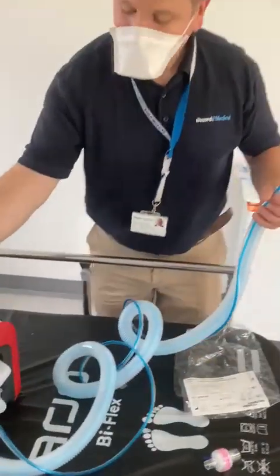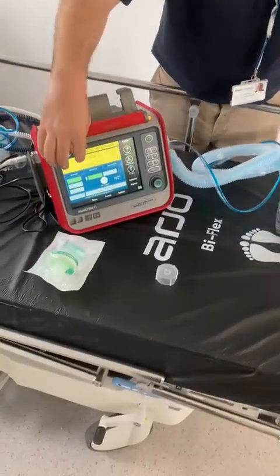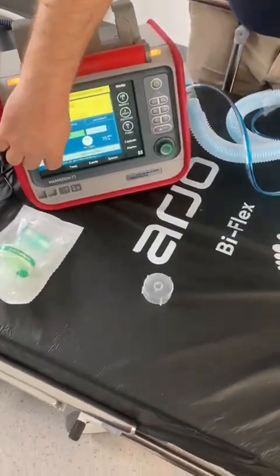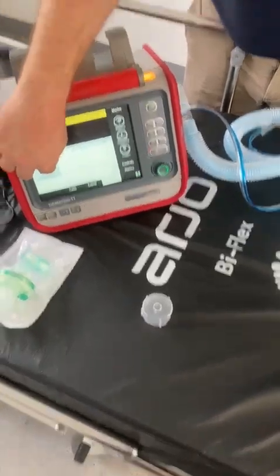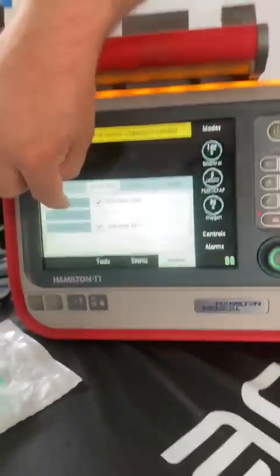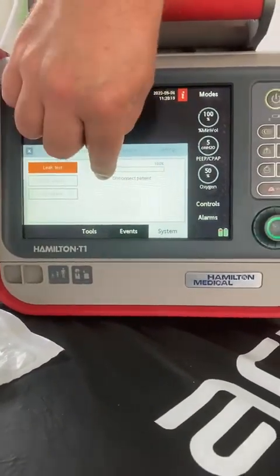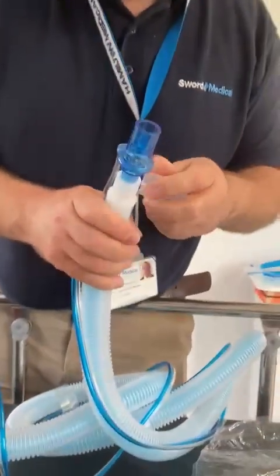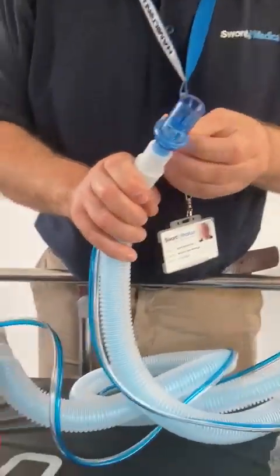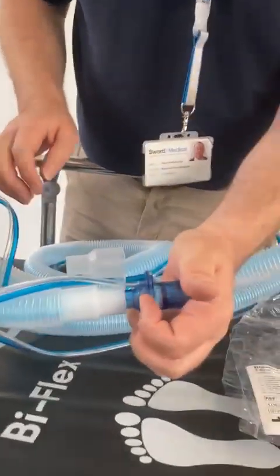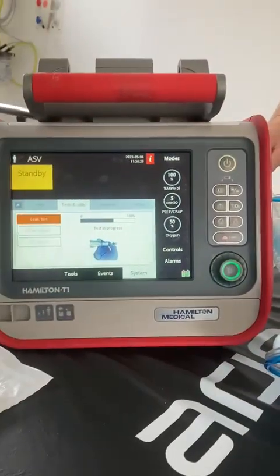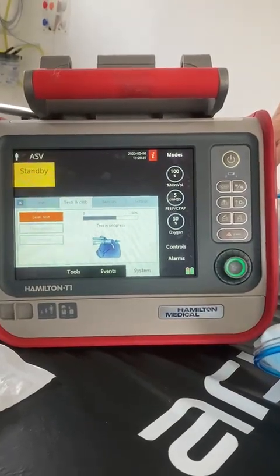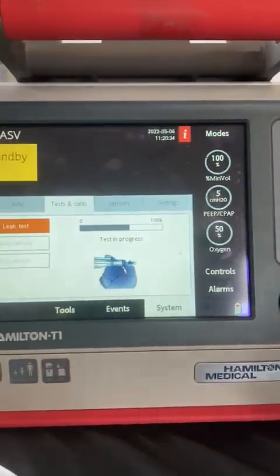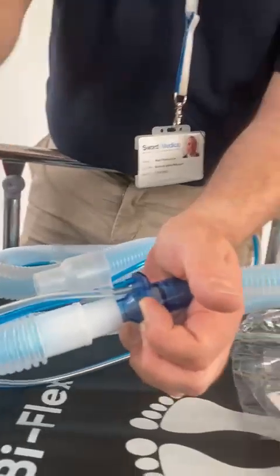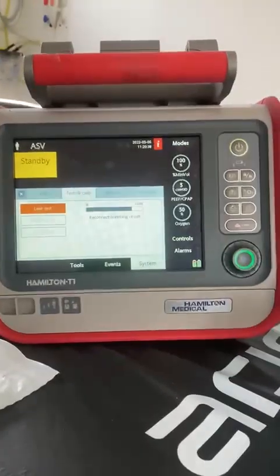So, the first test I'm going to do here, underneath the shortcuts, is the pre-op check. So the first test I'm going to do is my leak test. You hit leak test, it tells me to disconnect the patient, and when you're prompted to block the breathing circuit, you just occlude the circuit with your hand, and then it says test in progress, and it's just looking for a leak anywhere along the circuit, and then hopefully we'll get a green tick and the date and the time.